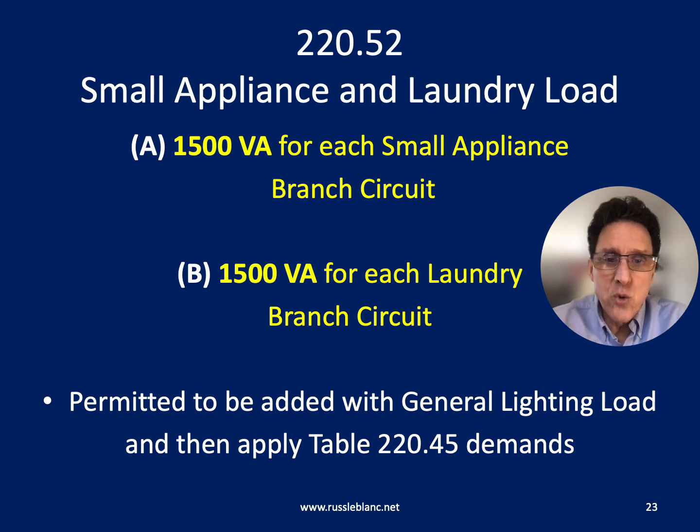Now, a couple of the nuances, if you take a look at 220.52(A), it says you're going to take each small appliance circuit and include a load of 1,500 volt amps per circuit, right? And it doesn't matter if it's a required circuit or an optional one, right? You're only required to have two small appliance circuits. But the way this is worded, if you install a third small appliance circuit, you have another 1,500 volt amps that you need to add to the calculated load.